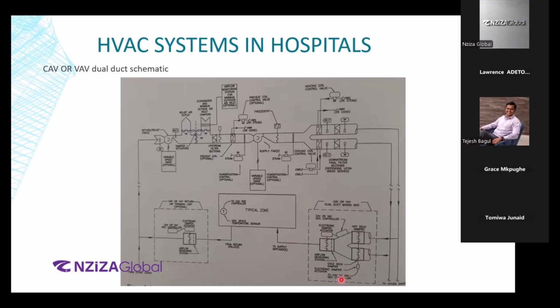Anyway, coming back to this system, the dual duct. Now the temperature of the air coming out is again properly calibrated with what is required at this set point over here. Okay. And then we have introduced another set of VAV box. Now this VAV box is on the return side.